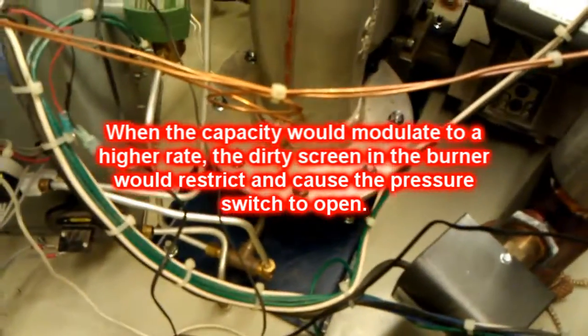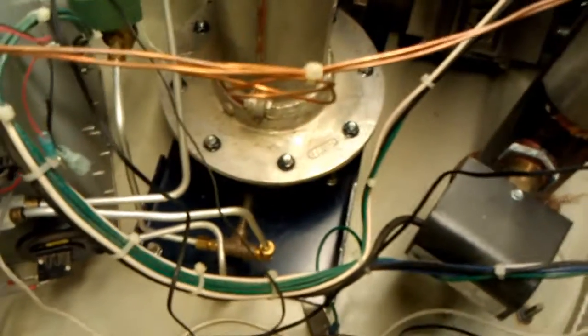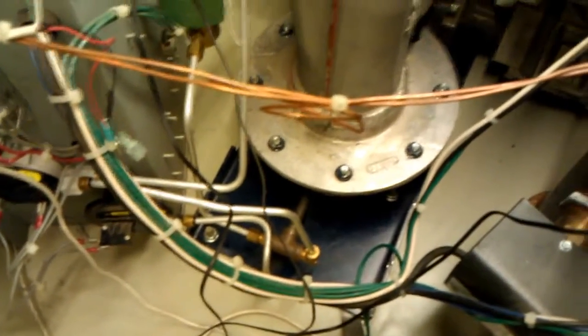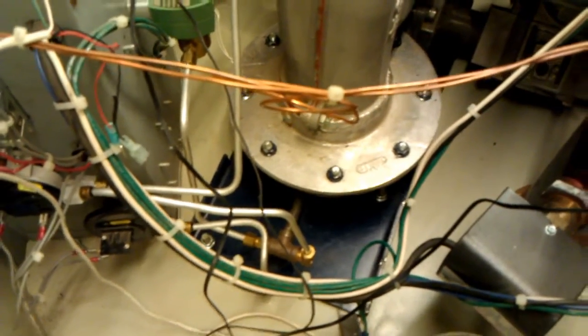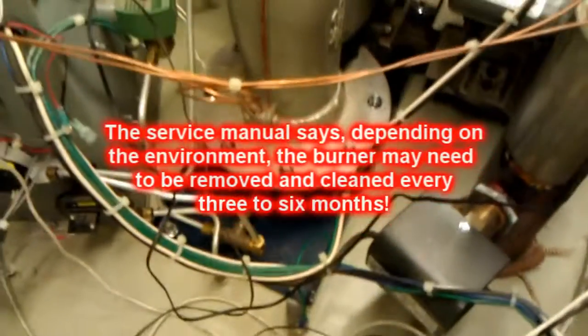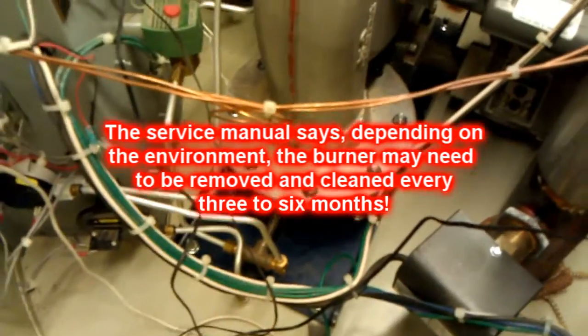That screen's got to be pulled and cleaned in the burner. This is like two years old. It probably needed it a couple months ago. So about every year, I guess this needs to be broken down and cleaned.